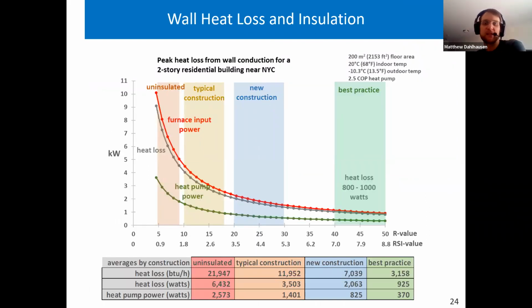Let's look at a simplified case of heat loss using just the wall conduction component. This will give a sense of what heating electrification will mean for the grid. This example is a 200 meters squared, or about a 2,100 square foot, 2-story house near New York City. We can calculate the heat loss during peak winter heating versus the wall assembly effective thermal resistance. The passive standard gives a total peak heat loss allowance of 2,000 watts for the entire building, including wall, roof and window conduction, air leakage, and ventilation air, which isn't shown here.